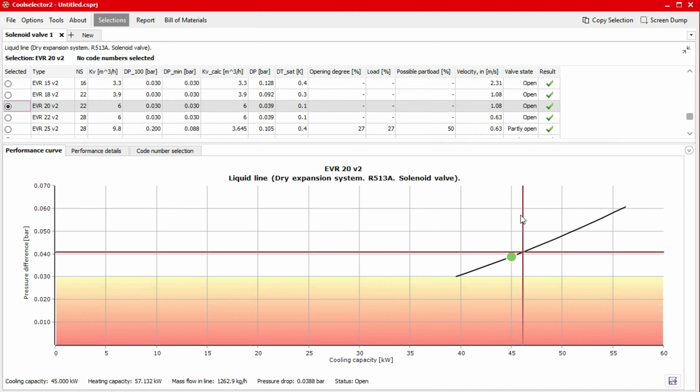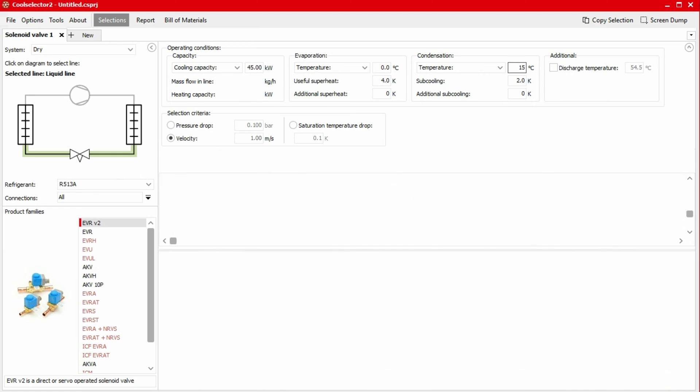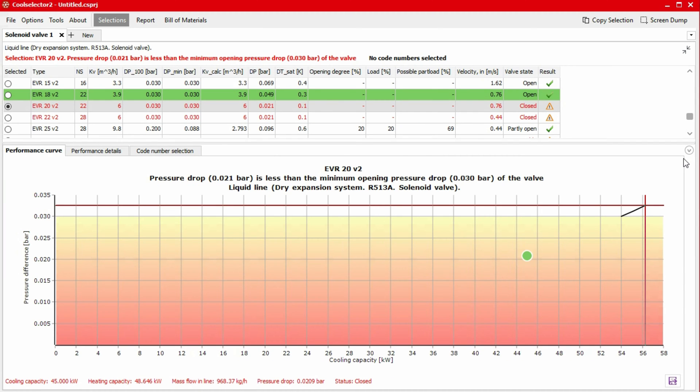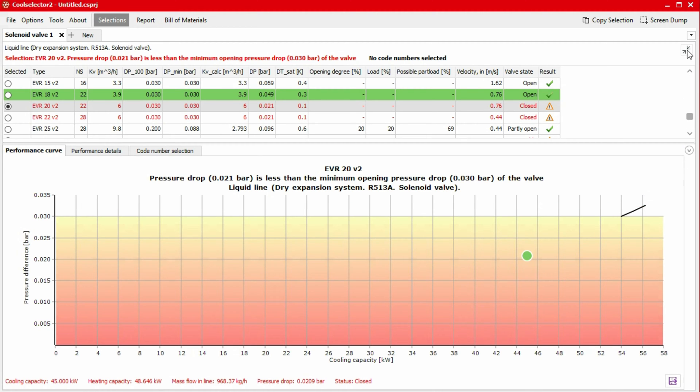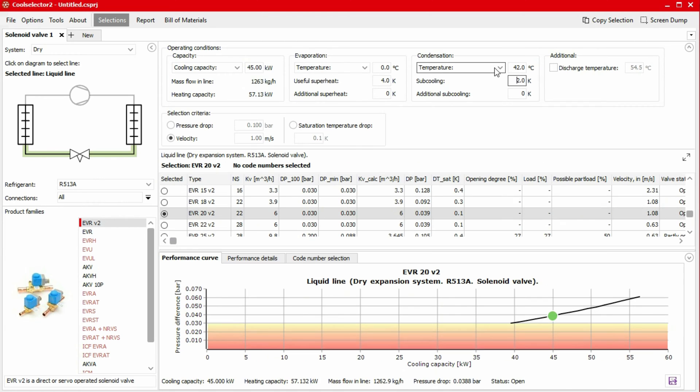Another important factor is the operating conditions over different periods of the year. If in our case, the winter temperature of the condenser is 15 degrees Celsius, we can see that the suggested valve would not function properly. This can result in higher load on the compressor or increase the condensation pressure during winter time and hence increasing our costs and decreasing the energy efficiency.